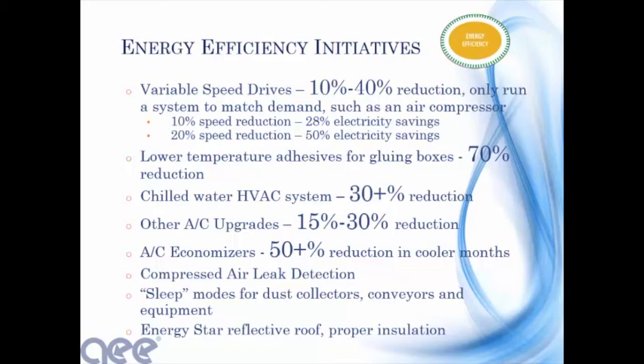Air conditioning economizers. The economizer is basically using free air. If the outside air is cool enough, you can use that as a source instead of having the compressor run. In an office building, that may not be as much of an issue because if it's cold outside, you probably don't have the air conditioning on anyway. But for us in a manufacturing facility, our packaging floor with all the different glue units and shrink tunnels, we run the air conditioning 12 months a year. So when we put in the new chiller plant, we got economizers, and now for 3 months of the year, we have free cooling in that room that previously had been mechanically cooled. So that was a big savings in the wintertime. We still have to have the air handler powered, but the actual cooling process is free.